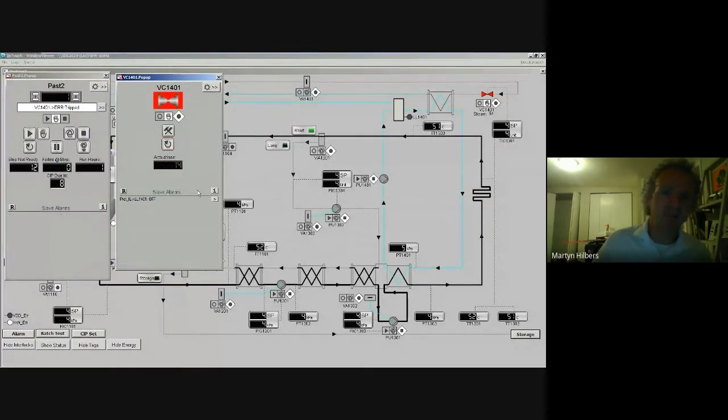It takes me to the control valve. I notice that I don't have any operator buttons anymore except for a reset and an out to maintenance. And what is my problem? Well, your problem is that you got a protection interlock, and that's caused by your level switch that has turned off. Now, that information I see here as well.